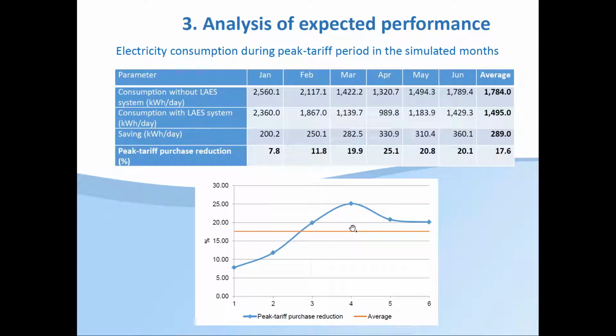Last of all, I wanted to point out the expected performance across the months. Since we are relying on things like solar energy, which is the most common case, there is a huge difference between January, April, and June depending on the location. So you can go from below 10% to plus 25% of the energy in the peak tariff that can be avoided.